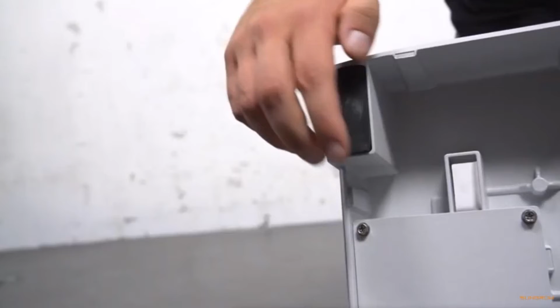With 33 kilograms, the individual modules are easy to handle by one person. They are designed to be installed in a simple plug-and-play style. Fix the modules on both sides with the included M5 screws. Next step is to connect the switchgear to the base. Slide it into the foreseen slot on the right side of the battery and fix it with the included M5 screw. Once all modules and the switchgear are in place, it's time to fix the battery on the wall.